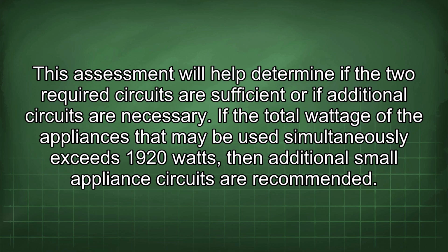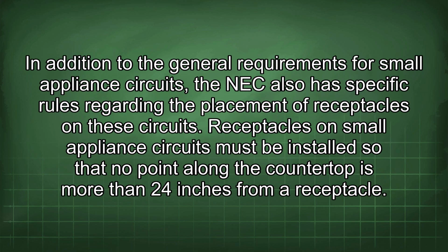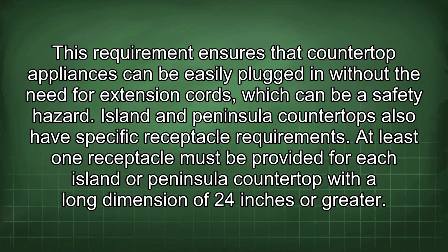In addition to the general requirements for small appliance circuits, the NEC also has specific rules regarding the placement of receptacles on these circuits. Receptacles on small appliance circuits must be installed so that no point along the countertop is more than 24 inches from a receptacle. This requirement ensures that countertop appliances can be easily plugged in without the need for extension cords, which can be a safety hazard.